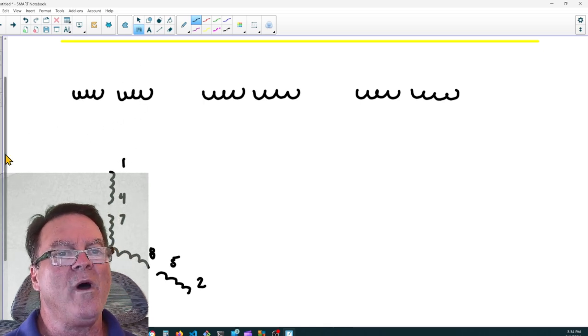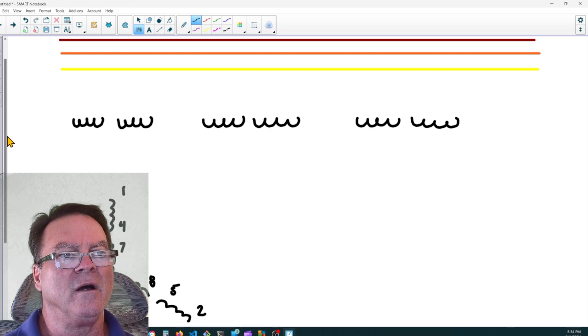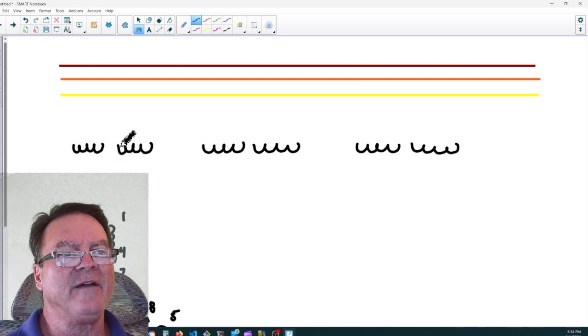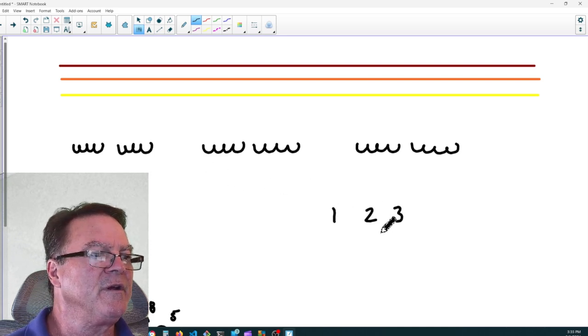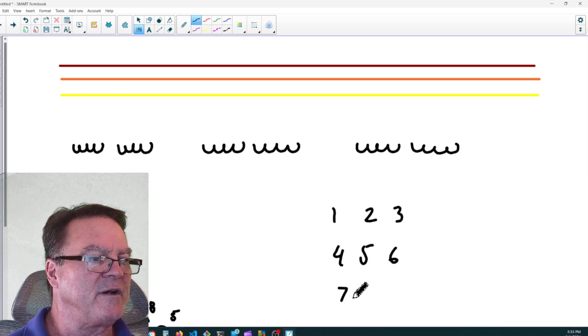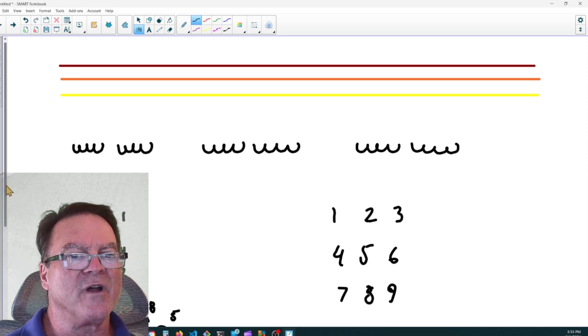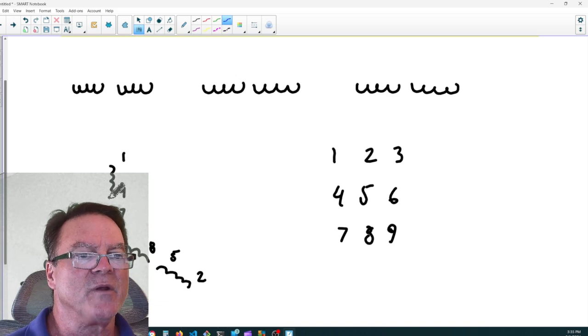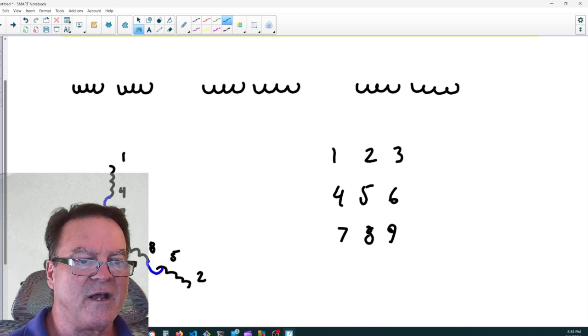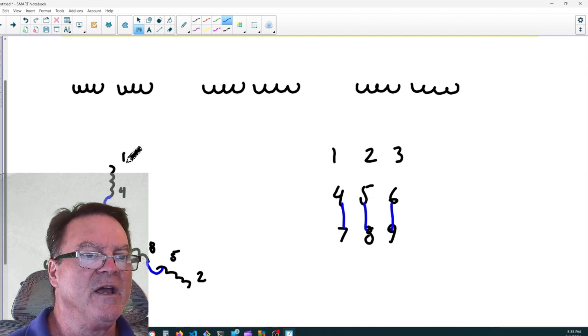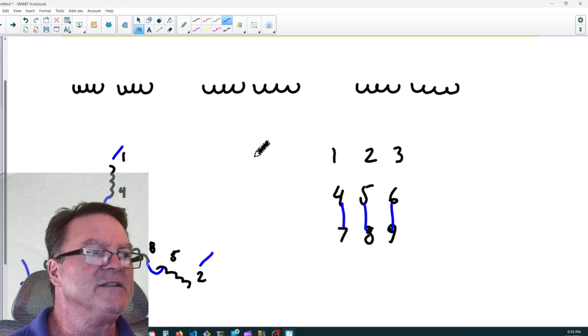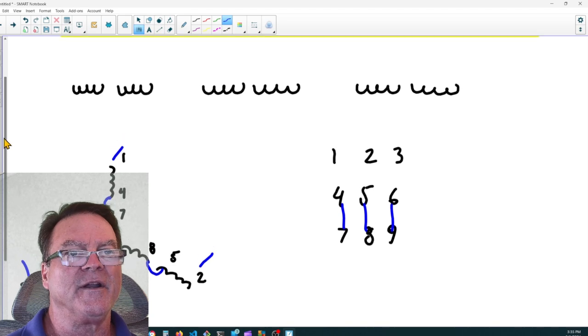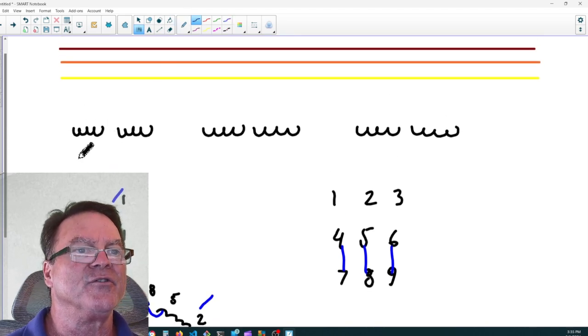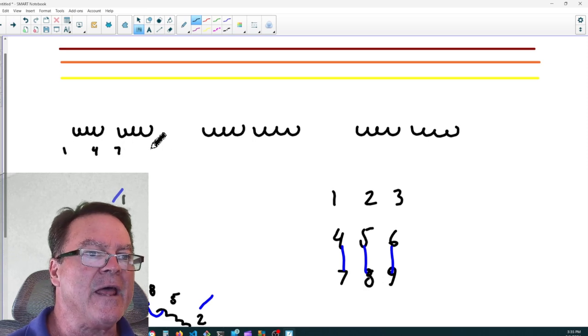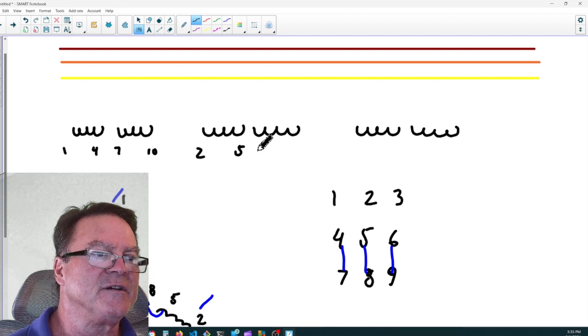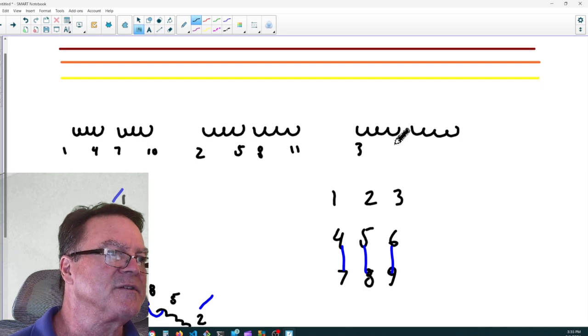So that if I wanted to connect this motor in high voltage, 1, 2, 3, 4, 5, 6, 7, 8, 9. If I wanted to connect this motor in high voltage, I would hook it up in series. So I'd put a jumper between 4 and 7, 5 and 8, and 6 and 9. So 4 to 7, 5 to 8, 6 to 9. And 1, 2, and 3 would be my leads out. So on here, and I'll have to draw the numbers small, we have 1, 4, 7, 10. Well, that 10 is already used. 2, 5, 8, 11, 3, 6, 9, 12.